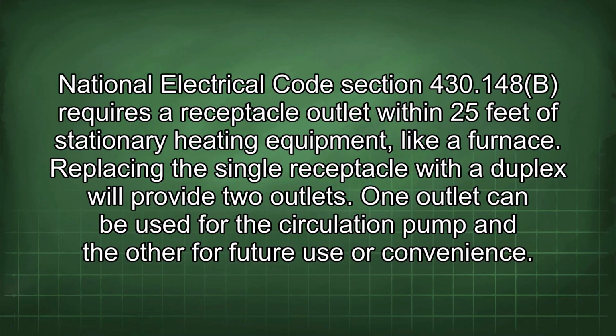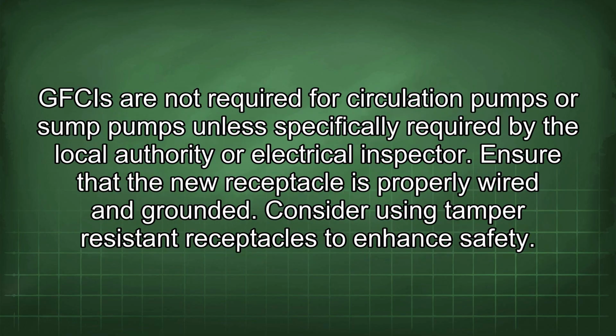National Electrical Code Section 430.148b requires a receptacle outlet within 25 feet of stationary heating equipment, like a furnace. Replacing the single receptacle with a duplex will provide two outlets. One outlet can be used for the circulation pump and the other for future use or convenience. GFCIs are not required for circulation pumps or sump pumps unless specifically required by the local authority or electrical inspector.